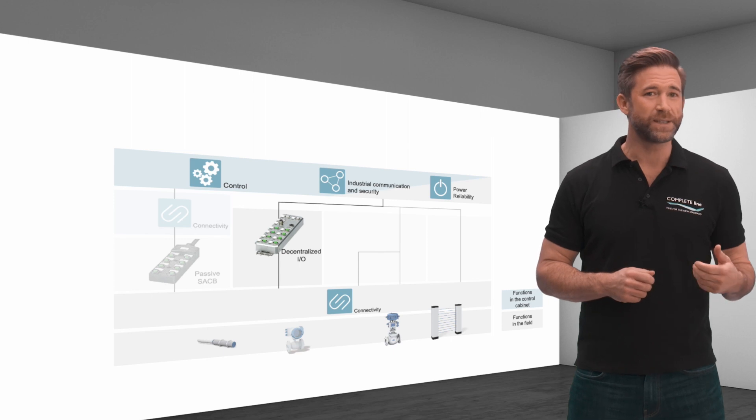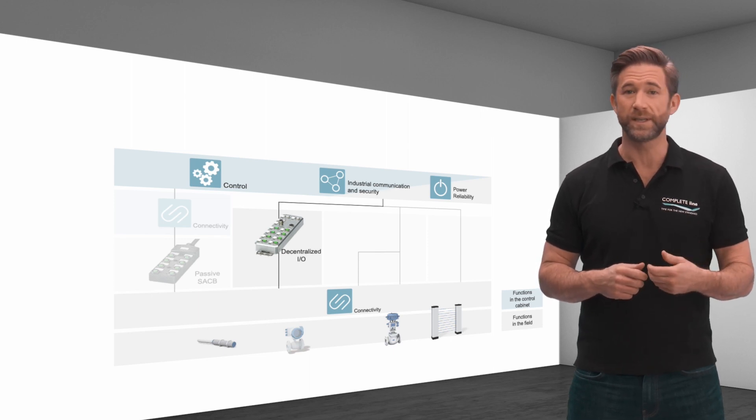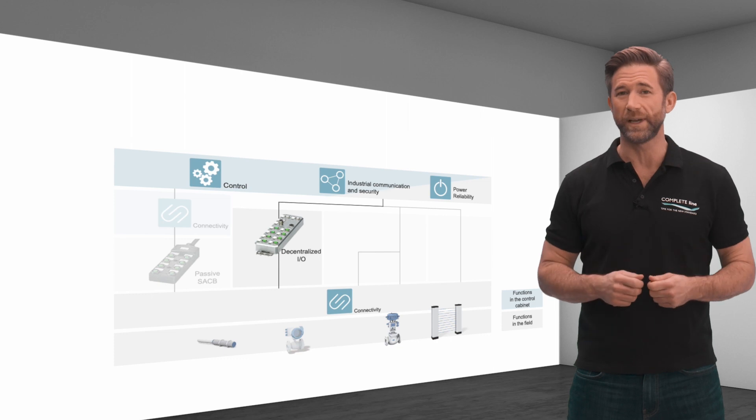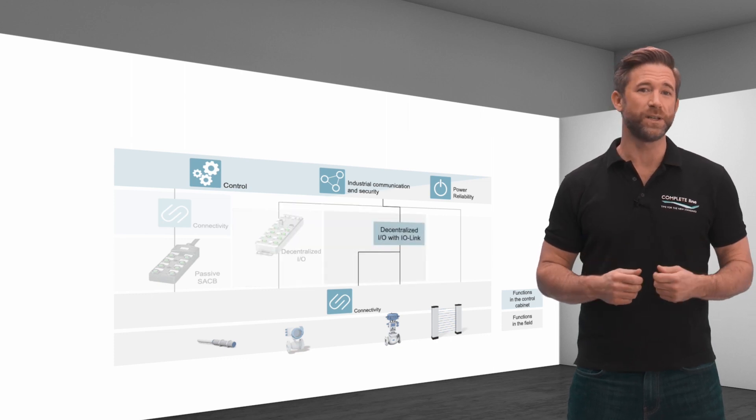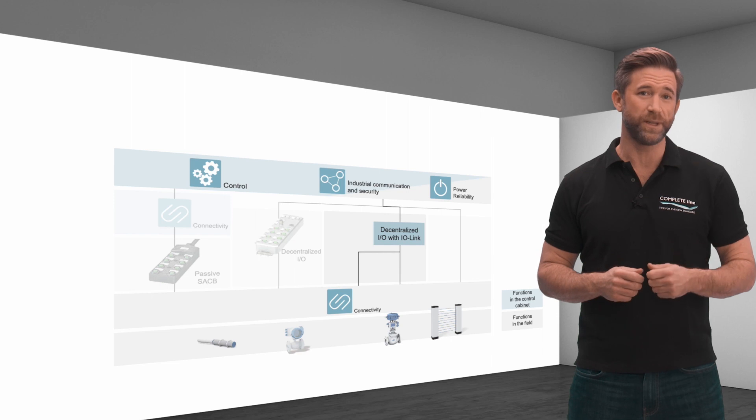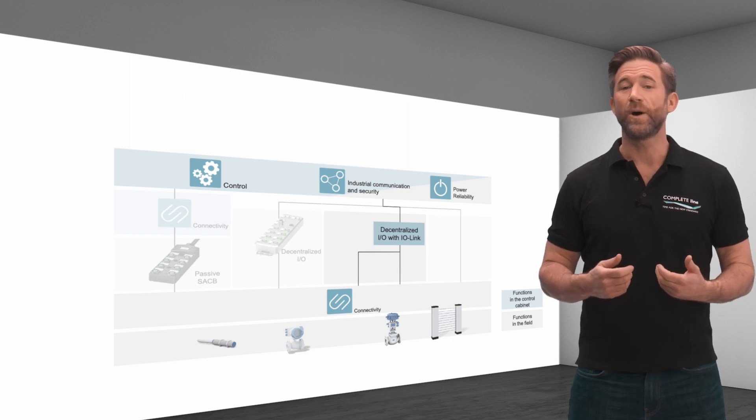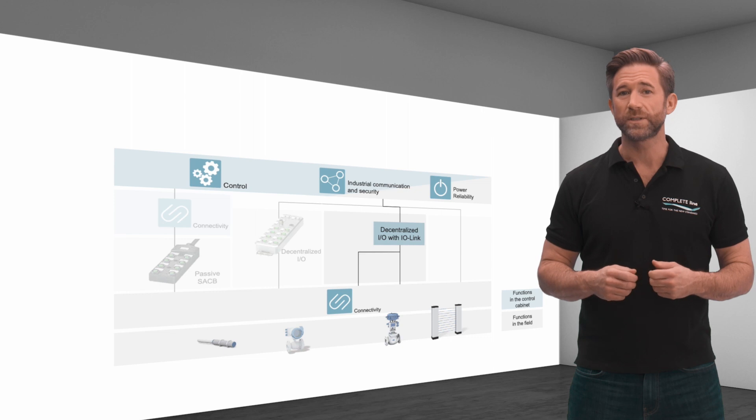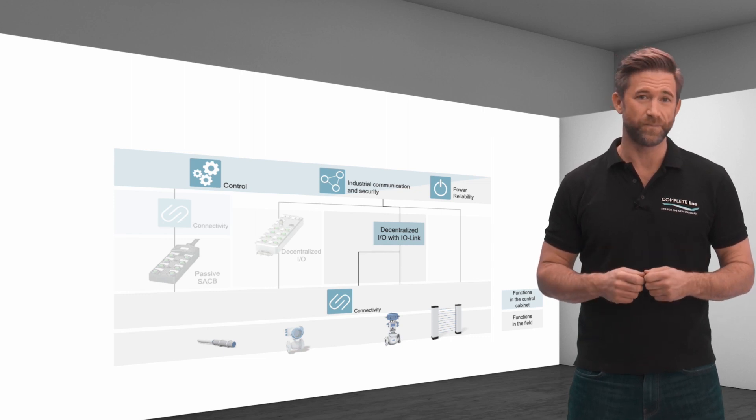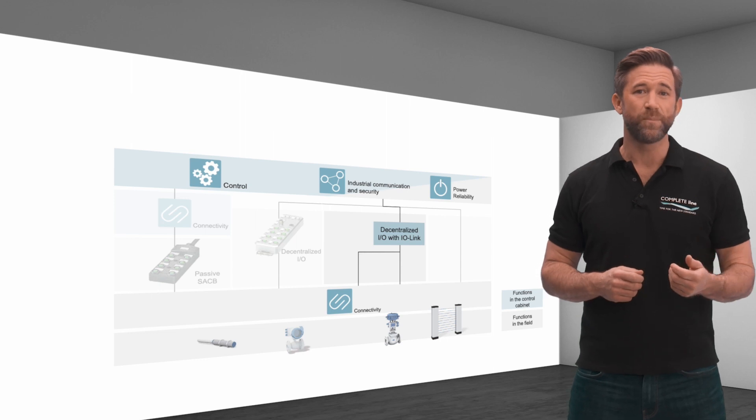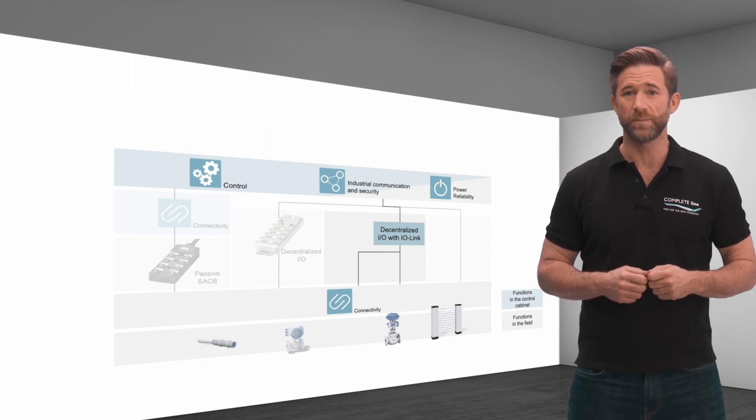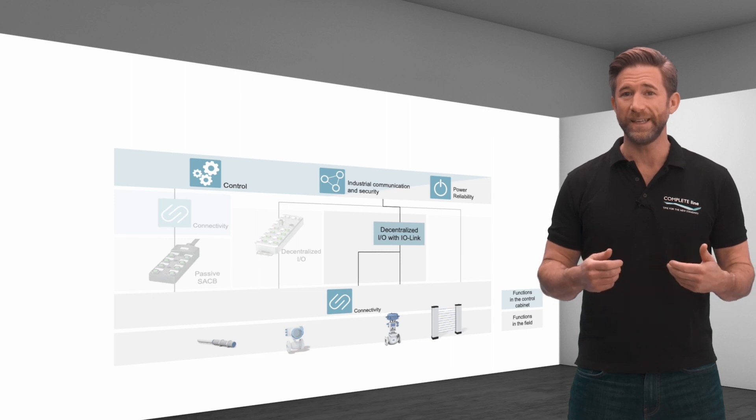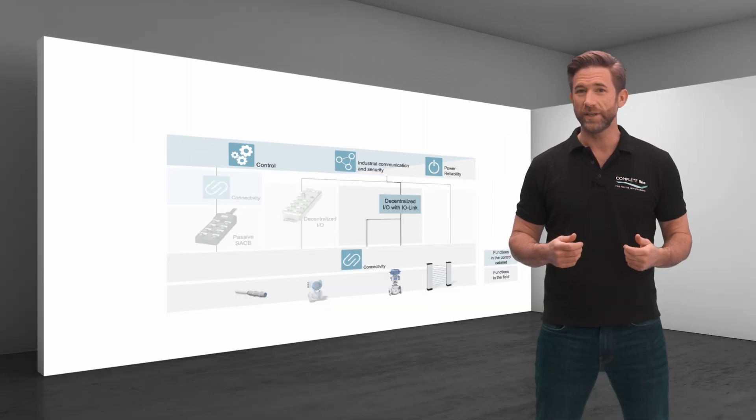They collect signals and forward them, including signal source information to the controller. IO-link technology adds further possibilities. The globally standardized IO interface enriches communication with process and service data. This makes it possible, for example, to detect the degree of sensor contamination and plan cleaning at an early stage.